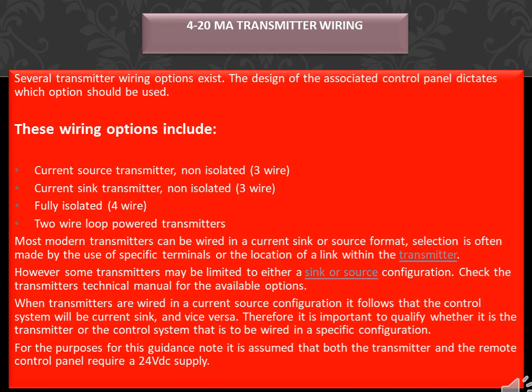Several transmitter wiring options exist. The design of the associated control panel dictates which options should be used. These wiring options include: current source transmitter non-isolated 3-wire, current sink transmitter non-isolated 3-wire, fully isolated 4-wire, and 2-wire loop-powered transmitters. Most modern transmitters can be wired in a current sink or source format, with selection often made by the use of specific terminals or the location of a link within the transmitter.